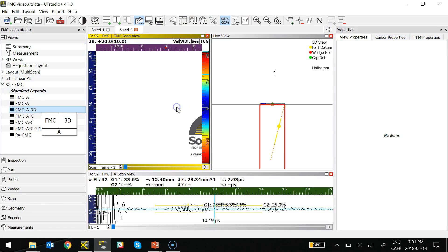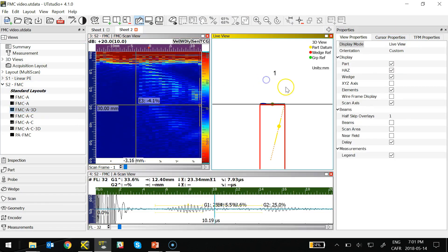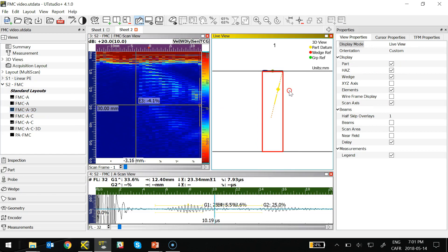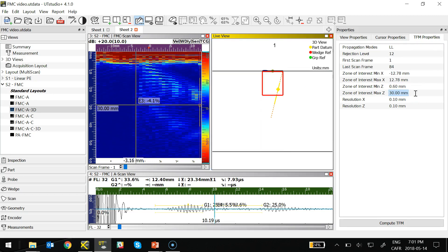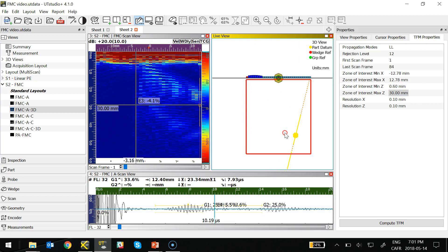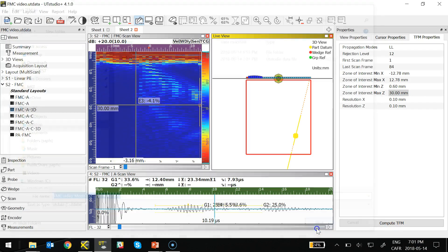Now, the first view I'm going to introduce you to here is the Live 3D view. In this 3D view, you see that there is a big red square over the part. What I'm doing with that red square here, this will be the zone where I'll be computing my TFM images.